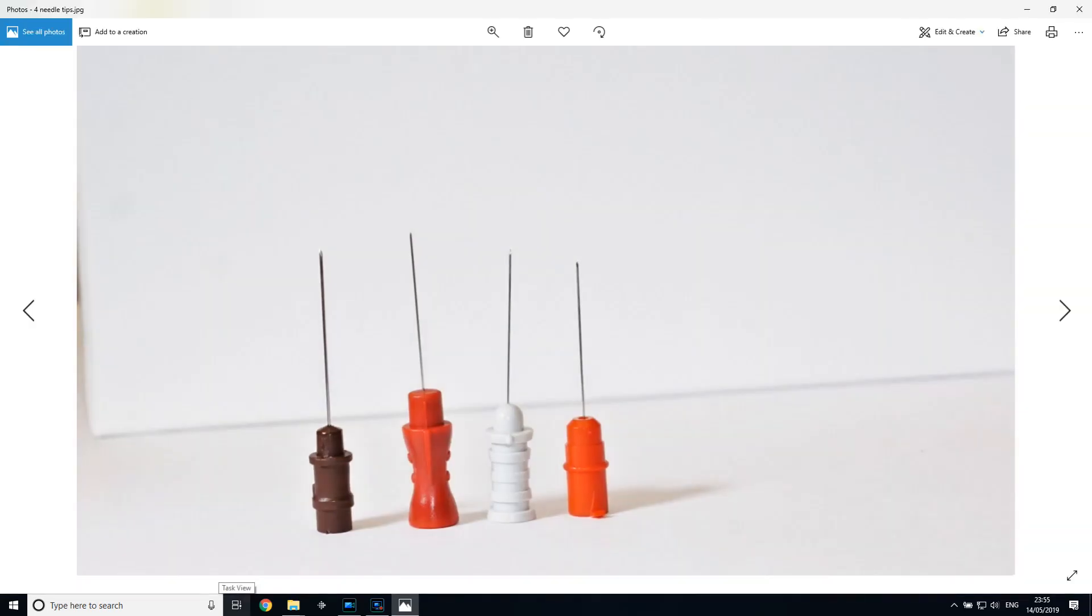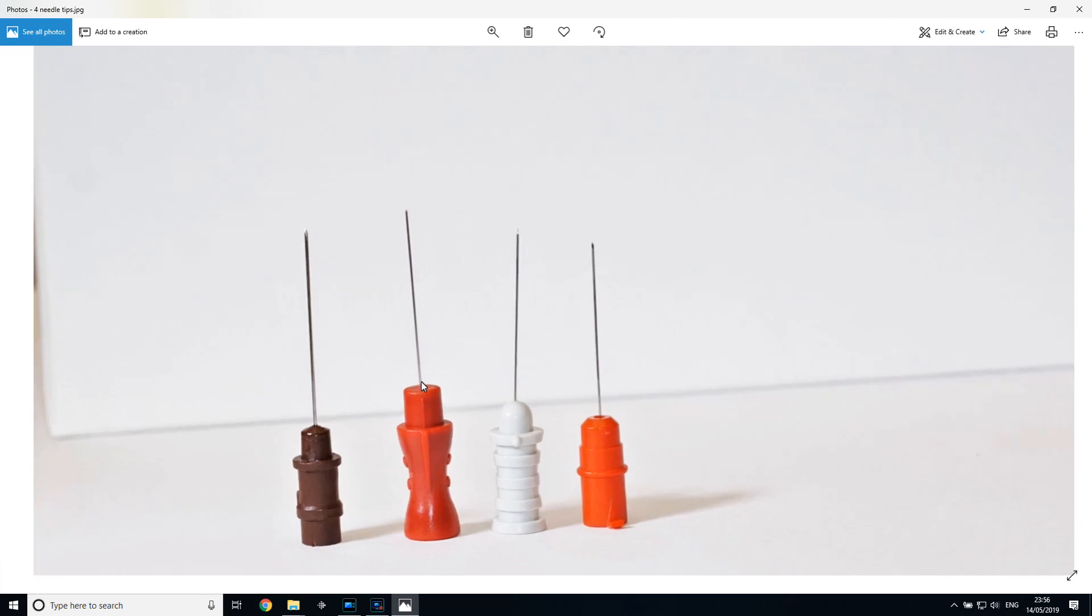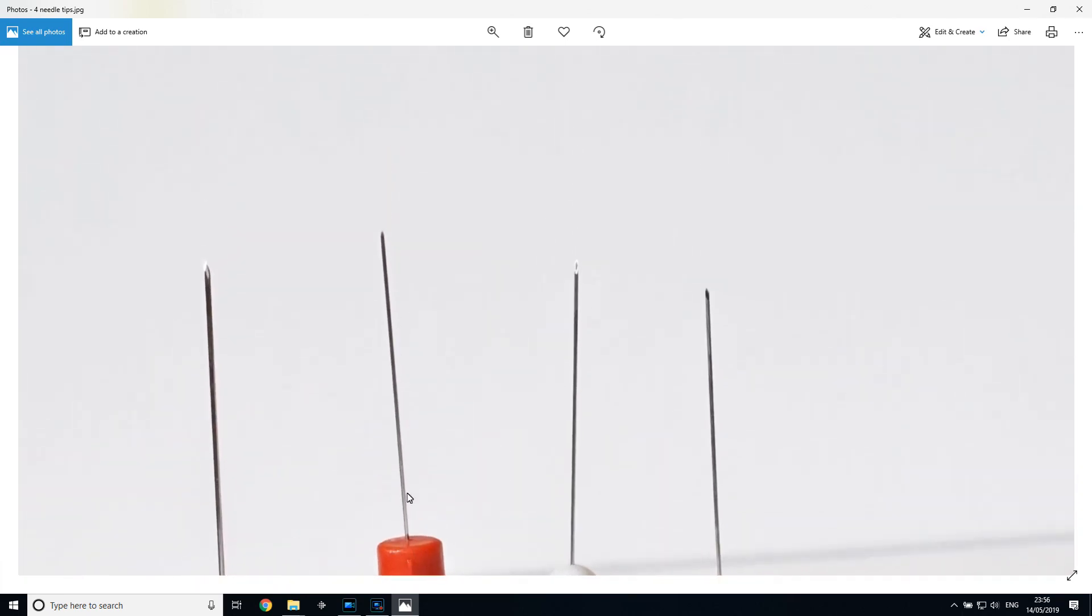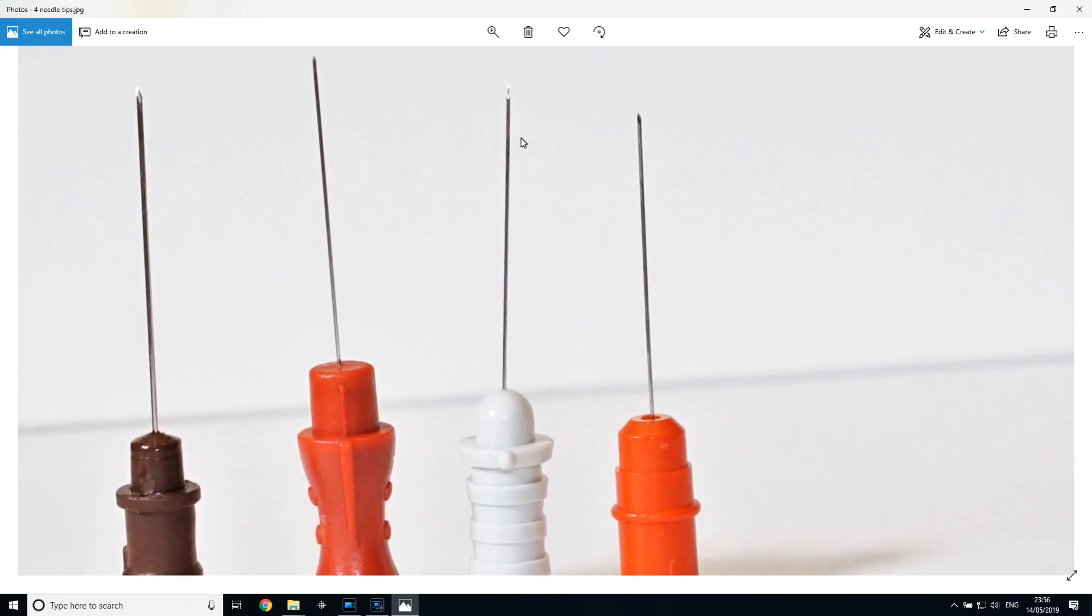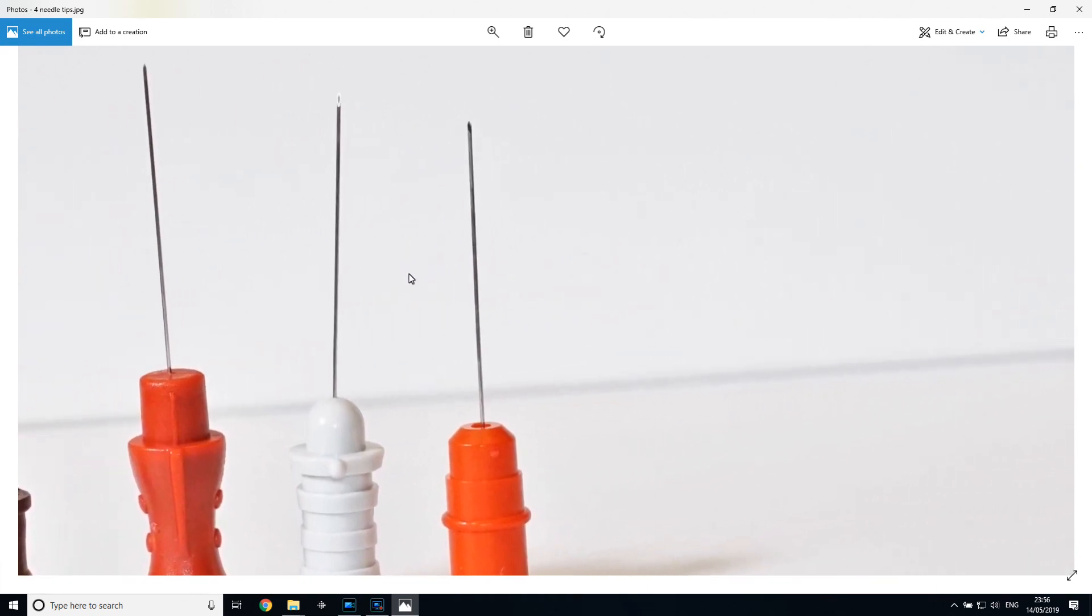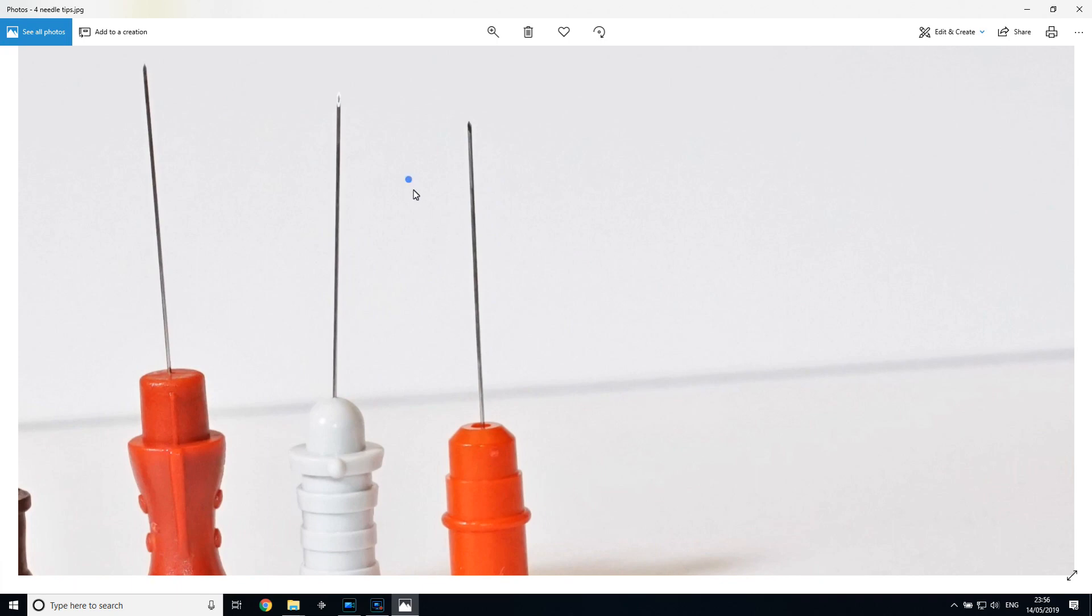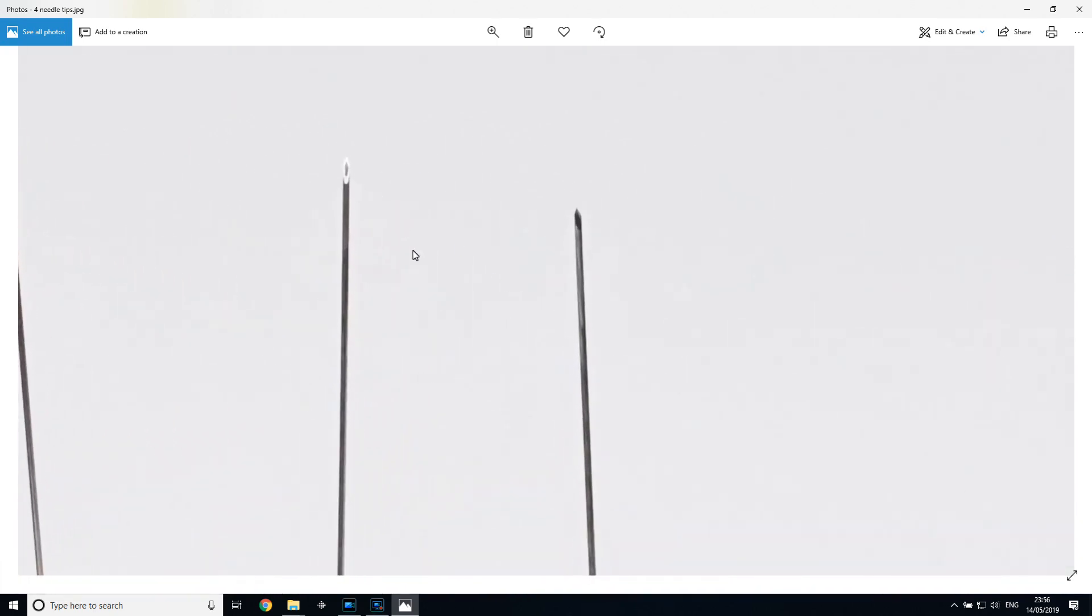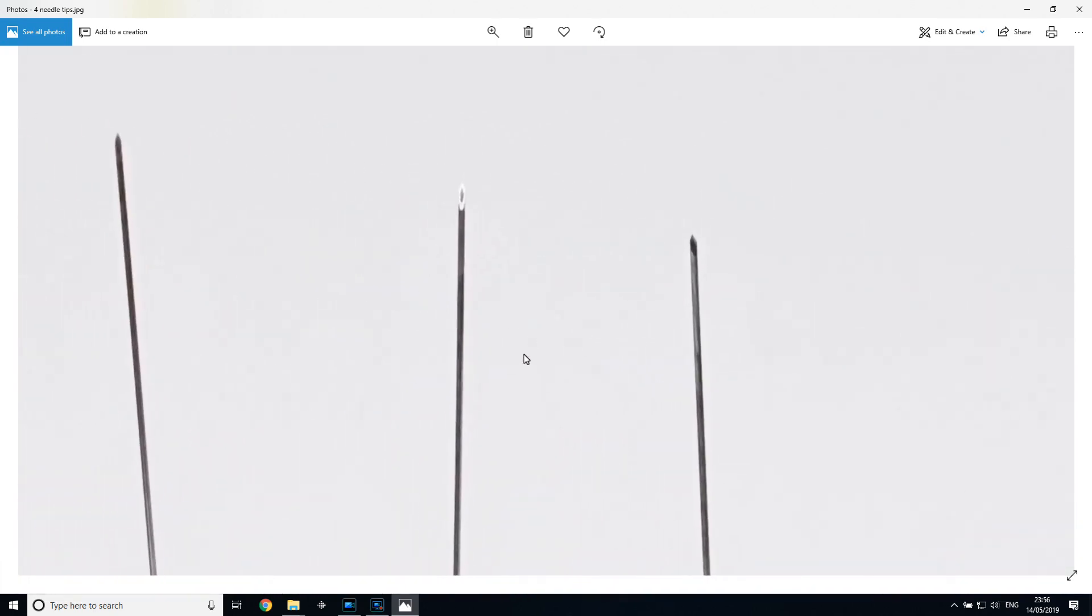Let's move on now and compare the needle tips between the three facial needles and the true single fiber EMG needles. So the one, that second on the left here, that's the Technomed one. Let's just zoom in on that. So that's also 0.3mm in diameter. The Ambu one we've already seen in some detail, also 0.3mm diameter. And this is the Tecca one, also 0.3mm in diameter. Let's focus in on the tips. I've already mentioned that the depth of field is actually incredibly tight.